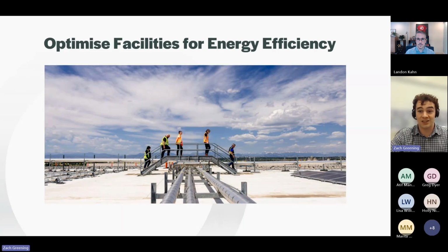Energy optimization doesn't stop at HVAC systems and lighting. There's also a lot to be said for the building envelope, which extends into how your space responds to heat, airflow, light, and occupancy. There are passive and semi-passive strategies that can significantly reduce the energy load on your systems, lower your operating costs, and improve thermal comfort with minimal ongoing input.